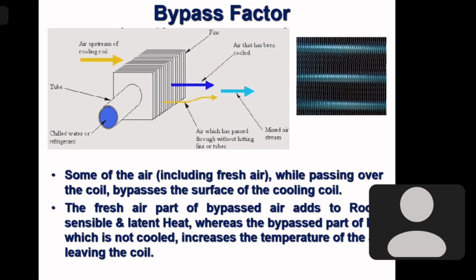And that bypass means, for the air coming out from the coil, if its temperature is, say, 12 degrees centigrade, the cooling coil temperature is normally around, say, 10 degrees centigrade. So a 10 degrees centigrade coil cannot produce 10 degrees centigrade cold air coming out from it because of some air bypassing, and there are other reasons also that I'll be discussing in the next slide, but for the time being let us consider it because of some air being bypassed.